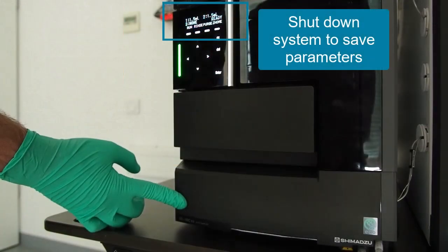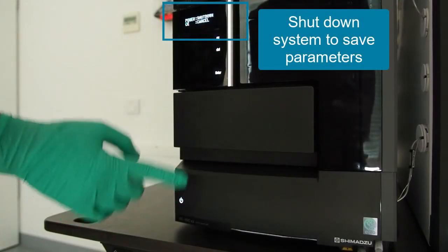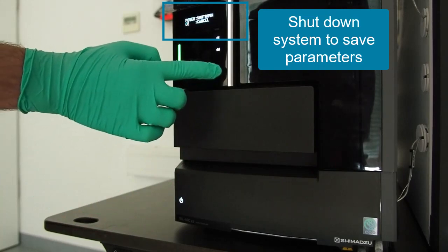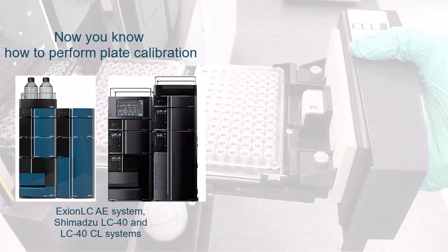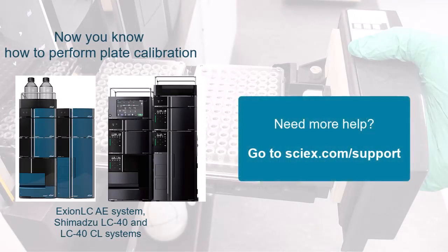Finally, shut down the system to save the parameters, so you do not need to repeat the procedure in case of mainboard issues. Now you know how to do a plate calibration for your auto-sampler. Go to sciex.com/support for further help on other topics.